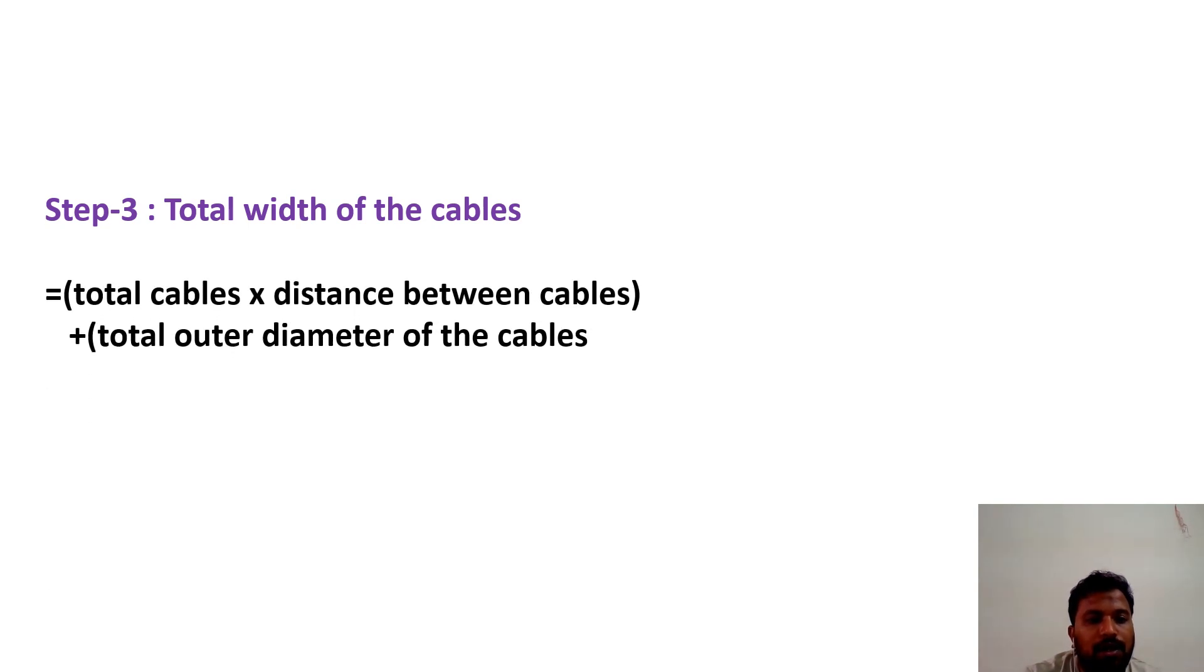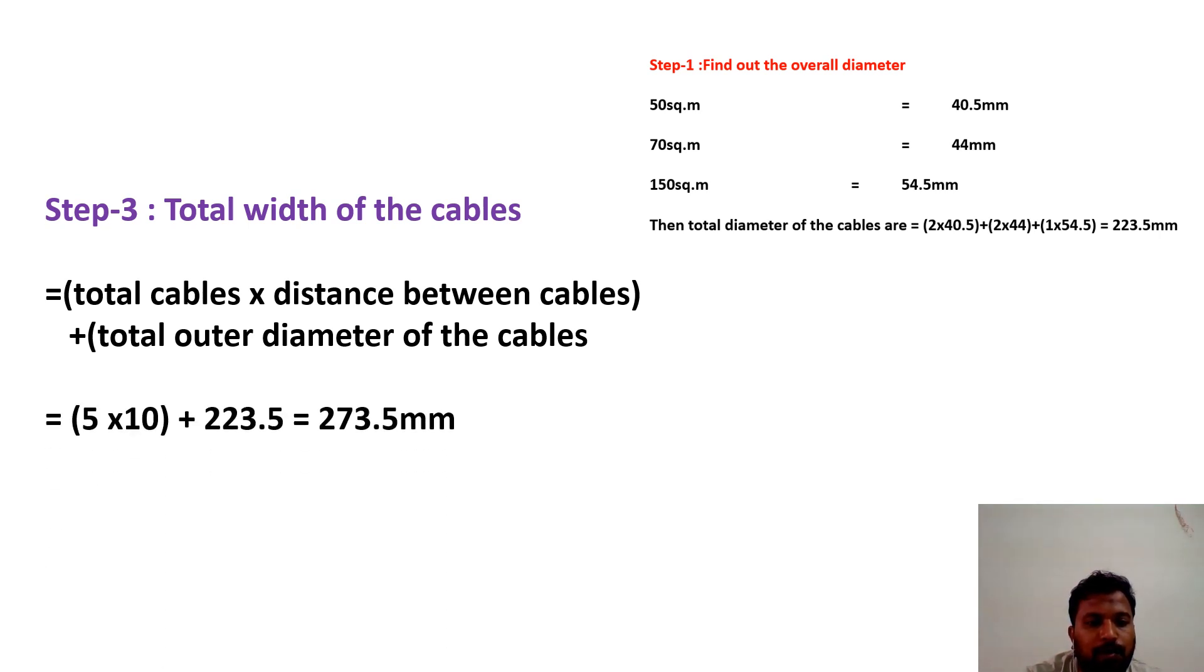What is the formula? Total cables into distance between the cables plus total outer diameter of the cables. From step 1, we got 223.5mm. How many cables we have? 2 number 50mm, 2 number 70mm, 1 number 150mm. Total 5 cables. Distance between the cables, in the example they say 10mm. Total number of cables, 5 into 10mm, this is the distance between the cables.